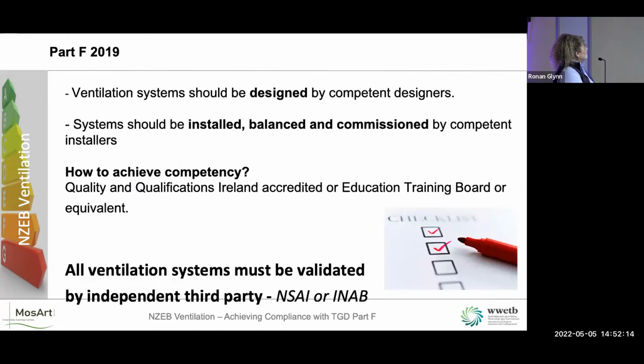So Part F states that ventilation systems should be designed by competent designers. They should be installed, balanced and commissioned by competent installers. And how to achieve competency? The easiest way is to come down to the WWETB and do the course. It's a really robust course, backed up by City and Guilds. The quality assurance is very good. And going forward now, all ventilation systems must be validated by an independent third party. So we can't drive that home enough.